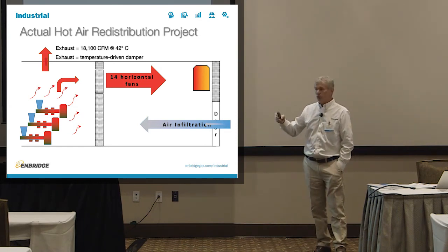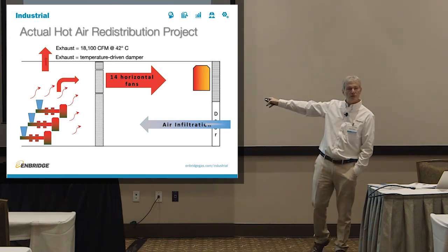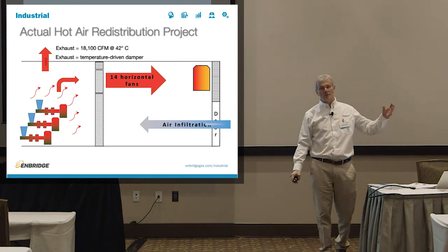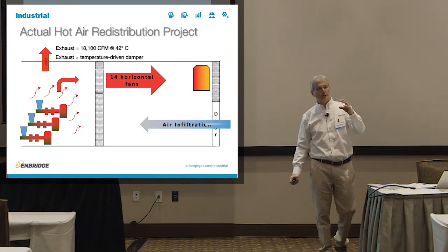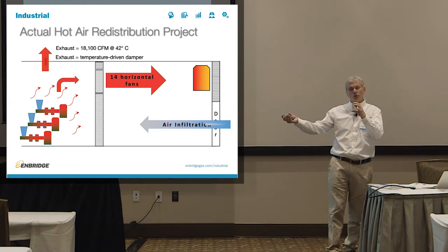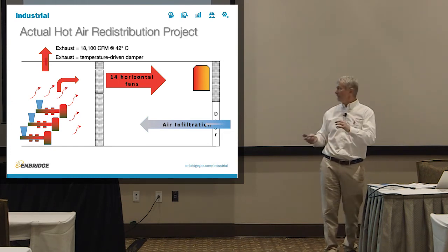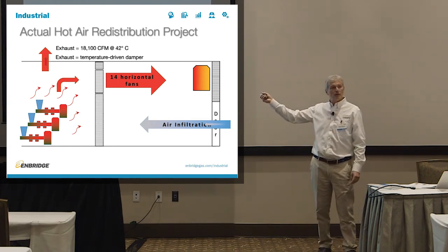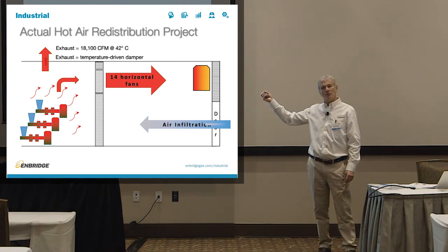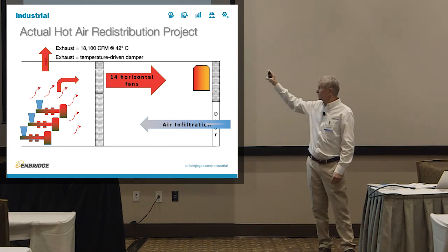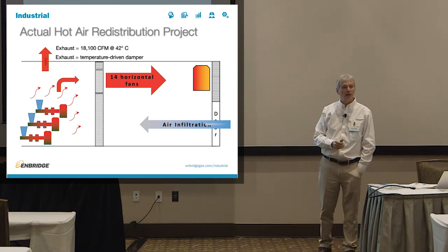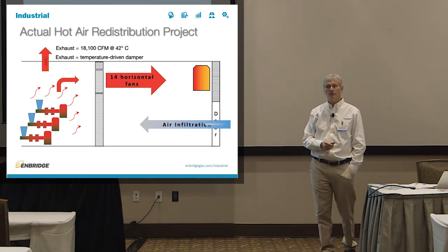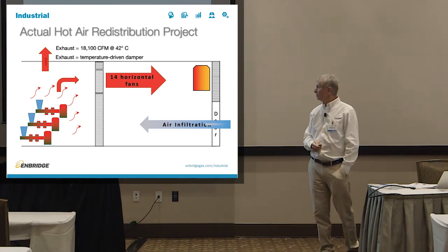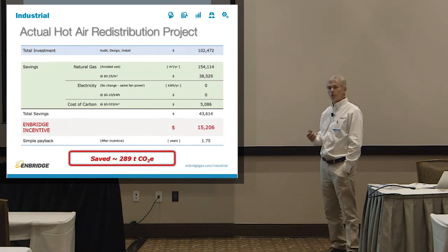What that allowed them to do is reduce the infiltration of the air, because now you have air coming from the hot side of the building, so there's not as much opportunity for the cold air to come in, and that air was heated. You had 18,000 CFM of nice, cozy 40 degrees Celsius air. Once redistributed, that was nice and warm, so they reduced the amount of the natural gas unit heaters that they needed in that space. So this was one of the more expensive projects.